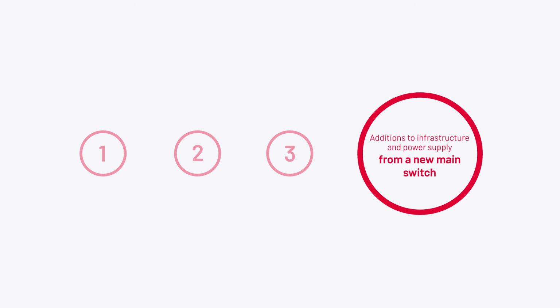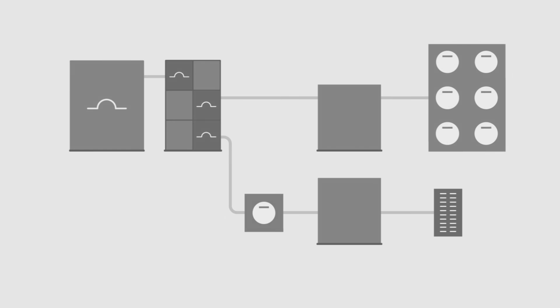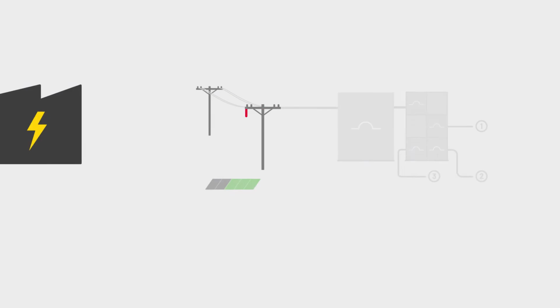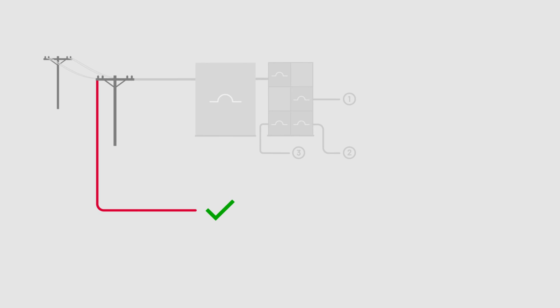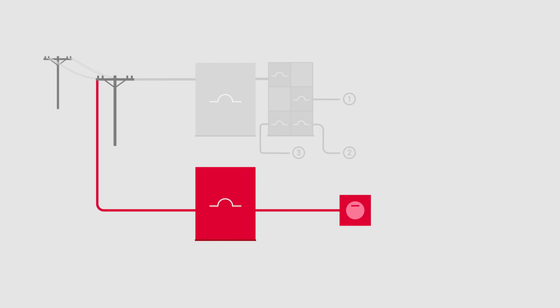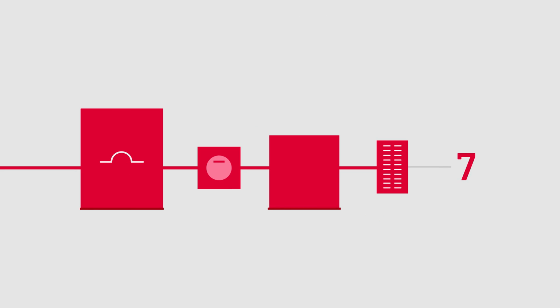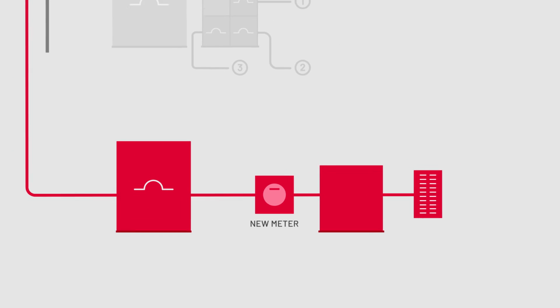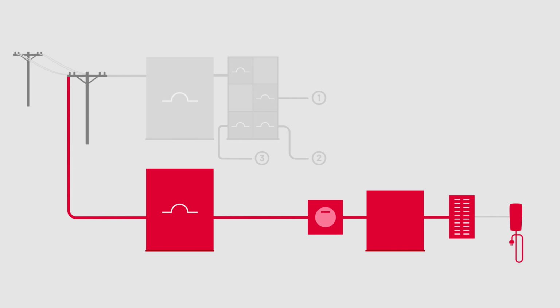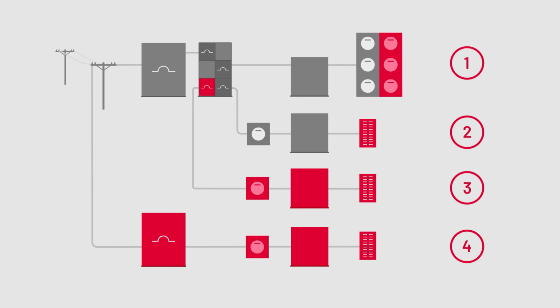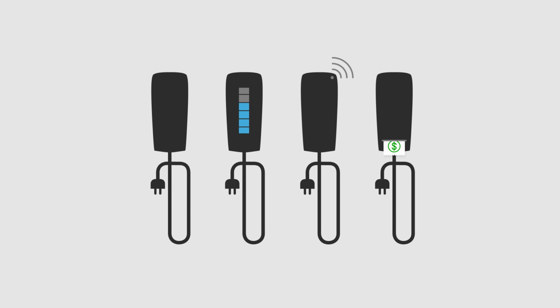Additions to infrastructure and power supply from a new main switch. If the unused capacity of the main switch does not permit supplying power to the desired number of charging stations, it will be necessary to contact the electrical utility distributor and verify that the network has enough capacity to power a new electrical input. If the answer is positive, it will then be possible to install a new main switch, a new meter, a new transformer, and a new electrical panel, which will allow the required number of charging stations to be supplied with power. Since a new meter has been installed, the electricity consumed by the charging stations will be billed to an independent account. Once the power source has been determined, it is then possible to choose the type of charging stations to be installed, as well as the billing method.